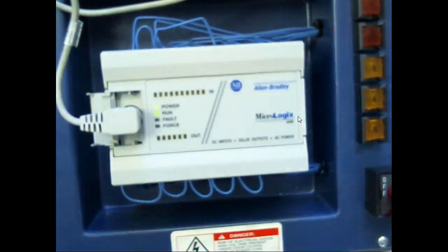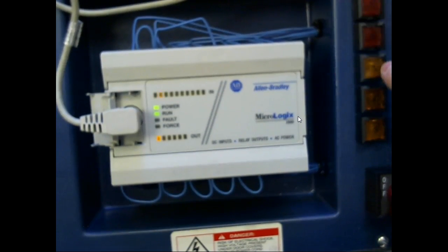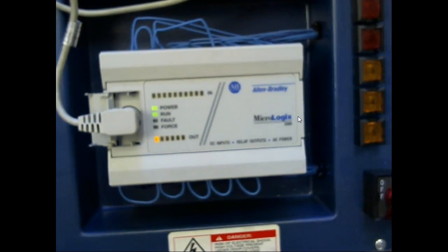So when I press an input, this has got a program in it, by the way. So see, when we press these inputs, and this is what's nice about a PLC, it gives you another tool for troubleshooting without pulling out your meter. So with motor control, to see if we were getting power to these guys, we'd have to get a meter out and read it. On here, if you press that button and that light turns on, then you know the wiring all the way from your input to your PLC is good. So you're through right there. And then I'll show you the monitor.